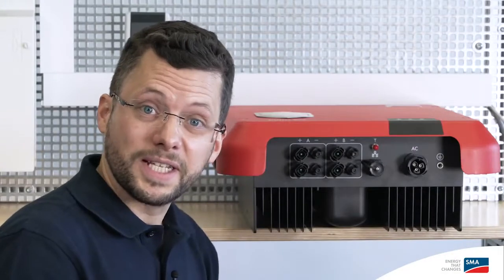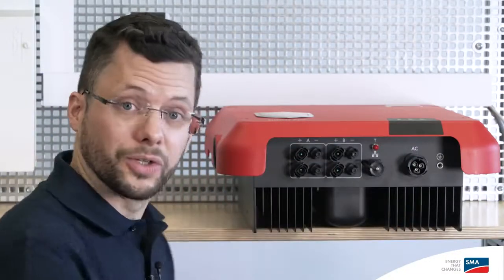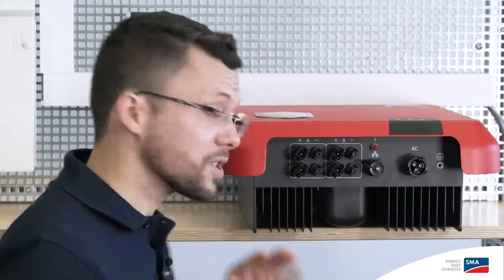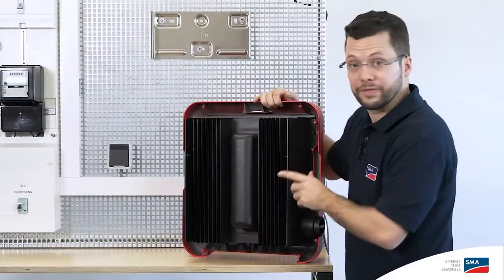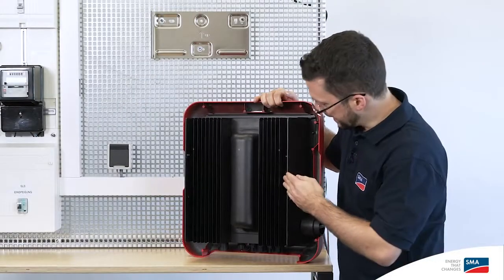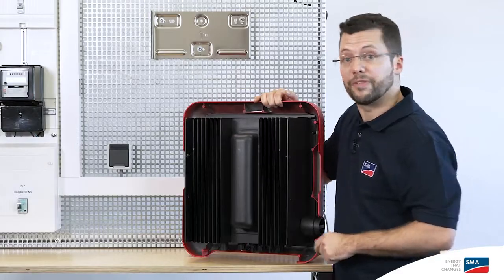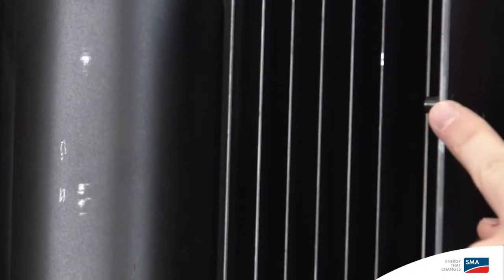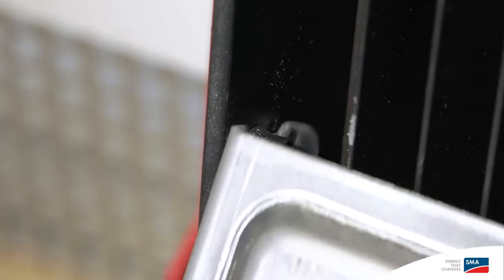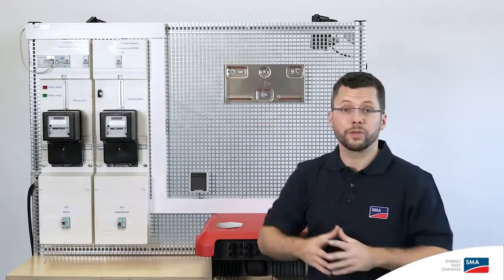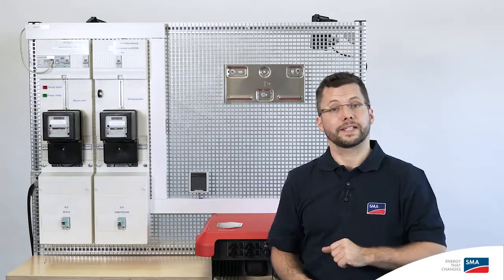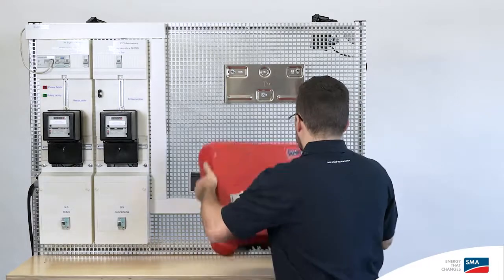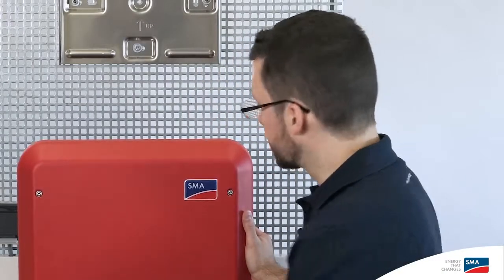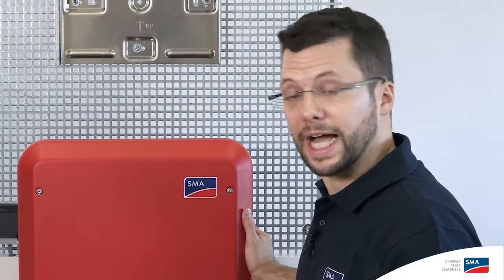The advantage of the Sunny Boy is that all connections can be accessed from the outside. This means that the cover doesn't have to be unscrewed. On the back of the inverter, on the inside of the outer cooling fins, there are guide pins on the left and right, which can be used to hang the inverter on the wall mounting bracket. I've already fitted the wall mounting bracket to the wall, and now I'll hang up the inverter. At 16 kilos, it's very light and suitable for one-man installation.